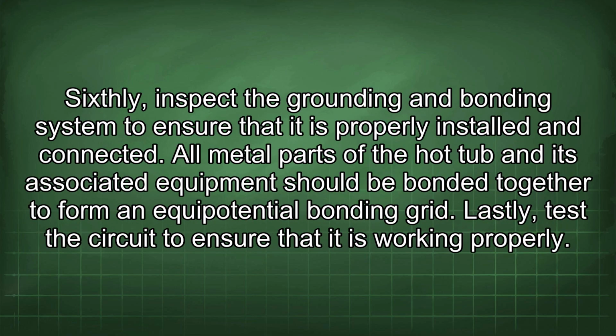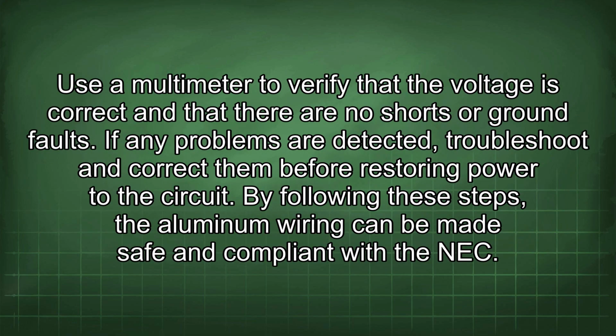Sixthly, inspect the grounding and bonding system to ensure that it is properly installed and connected. All metal parts of the hot tub and its associated equipment should be bonded together to form an equipotential bonding grid. Lastly, test the circuit to ensure that it is working properly. Use a multimeter to verify that the voltage is correct and that there are no shorts or ground faults. If any problems are detected, troubleshoot and correct them before restoring power to the circuit. By following these steps, the aluminum wiring can be made safe and compliant with the NEC.